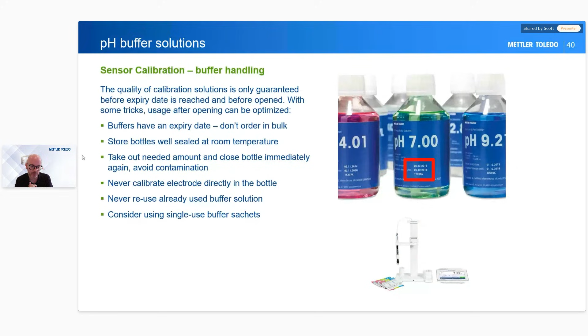Another thing to consider is using single-use buffer sachets, because they're really good at making sure that you have an accurate pH calibration all the time, instead of bottles. It might be something you want to consider longer term. And yet again, Mettler offer a range of these that I'll show you in a second. Here you can see a range of bottles, and these are the single-use sachets on this side. We do a different range, so you can find lots of different buffers.